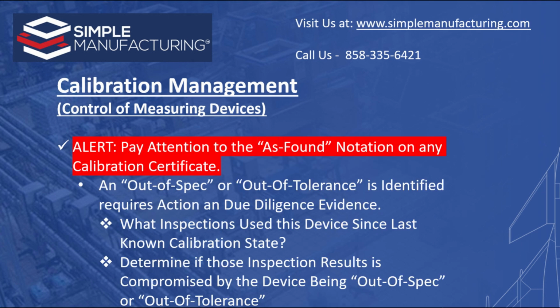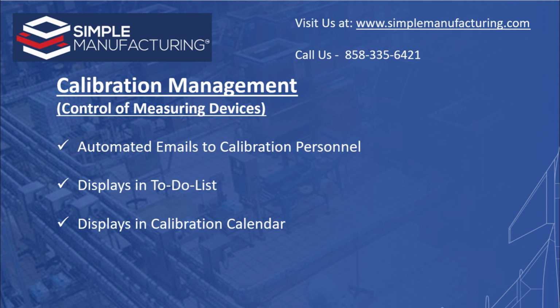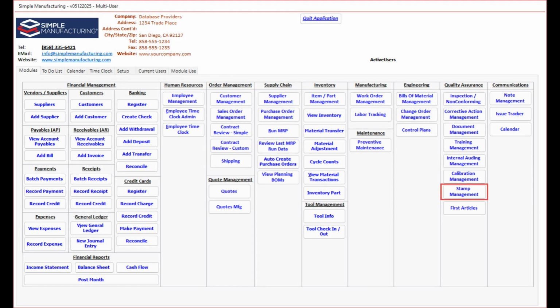Pay close attention to the as-found notation on the calibration certificate. When the as-found condition is out of tolerance, the action is identifying all product inspected by the device since the last known calibration from the inspection module, and determining if those inspection results are compromised by using an out-of-specification device. A thorough auditor will ask for evidence that this due diligence was performed. When using this module, calibration personnel will be alerted when calibration is coming due. In addition, alerts are displayed in the main menu of calibration as well as in the to-do list and in the global calendar.